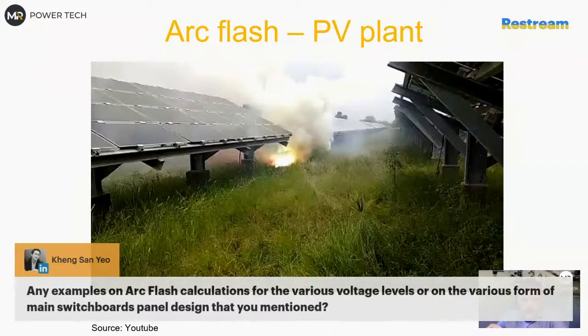And I can tell you that from my experience, if you work on medium voltage systems up to 36 kV, for example 11 kV to 36 kV, arc flash is usually not that big an issue. It is there, but because of the internal arc classification design of panels, it's not that we ignore it, we just acknowledge it. We are safe because we are in the range of the internal arc classification. Usually the protection is easy to adjust, so you can make it lower. I never actually had a medium voltage panel that was above 40 calories. They are usually somewhere between 2 and 20, and after adjustments they are getting better.